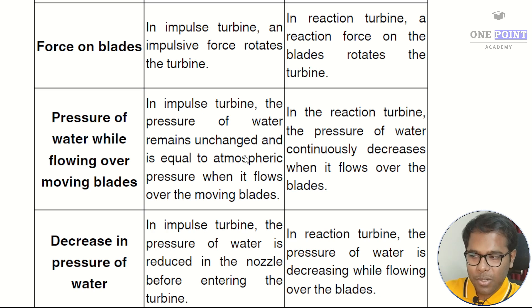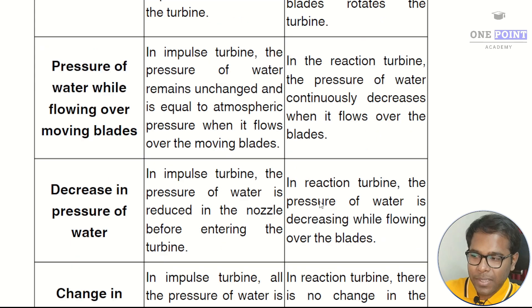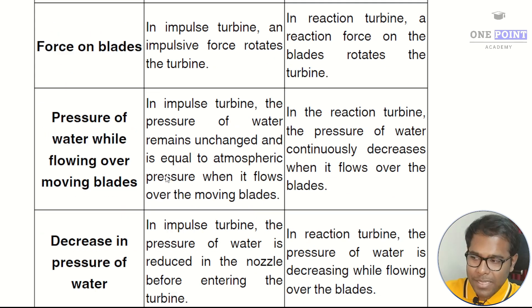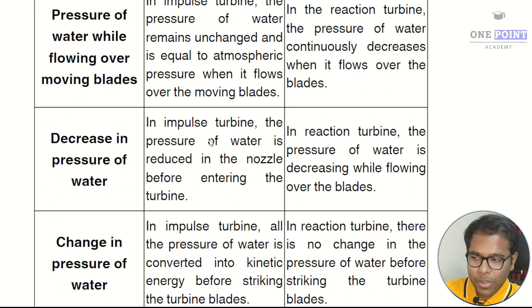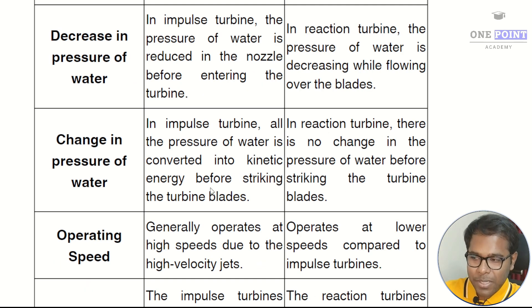The next difference is based on pressure of water while flowing over the moving blades. In an impulse turbine, the pressure of water remains unchanged and is equal to atmospheric pressure when it flows over the moving blades. In a reaction turbine, the pressure of water continuously decreases when it flows over the blades. Regarding decrease in pressure: in an impulse turbine, pressure is reduced in the nozzle before entering the turbine, whereas in a reaction turbine the pressure decreases while flowing over the blades.